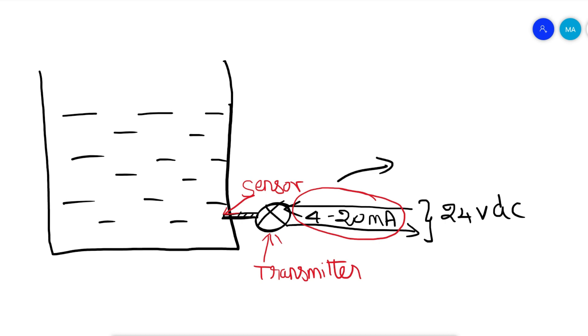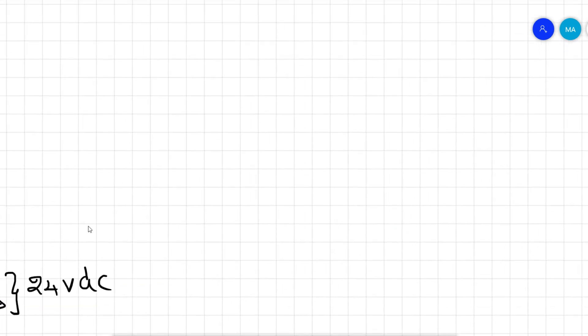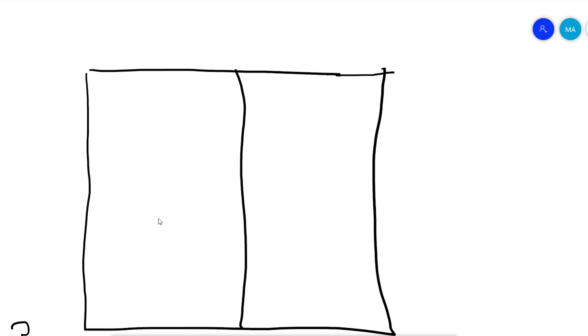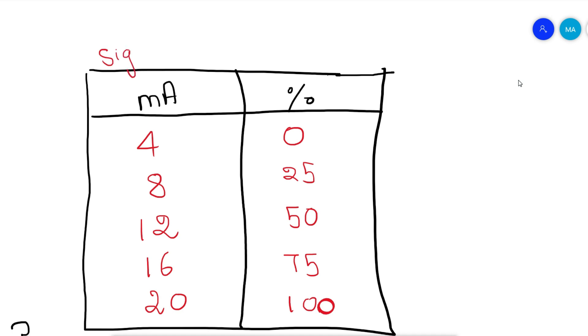So why should we use 4-20 milliamps signal? We know that a process parameter is sent as 4-20 milliamps signal from field to control room. This is how the percentage is related with 4 to 20 milliamps: 4 milliamps equals 0%, 8 milliamps equals 25%, 12 milliamps equals 50%, 16 milliamps equals 75%, and 20 milliamps equals 100% of the process parameter.